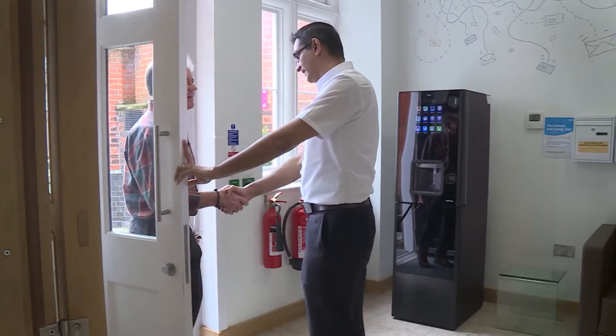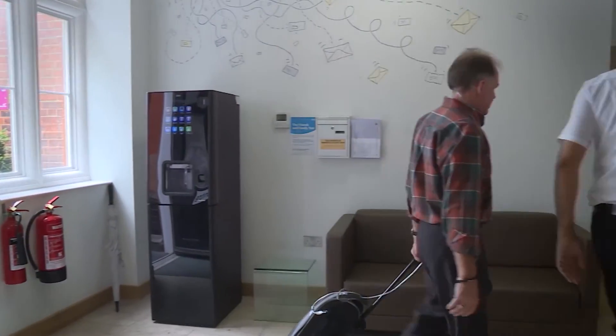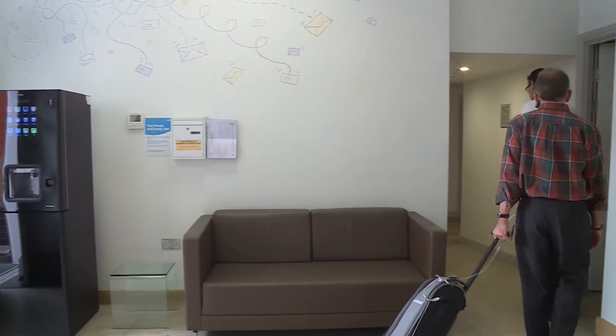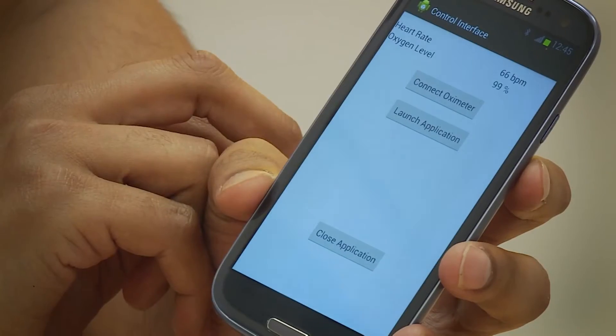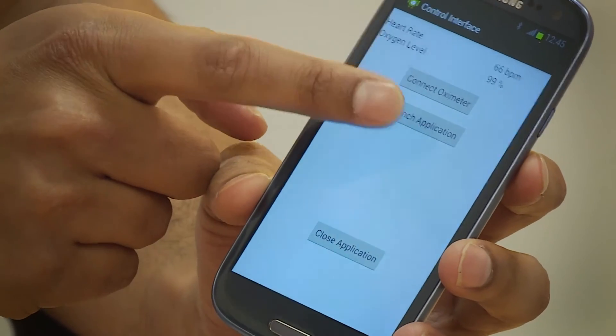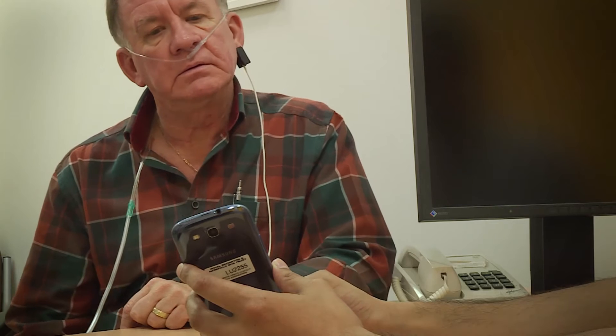So what we've devised together with our colleagues in biomedical engineering at Imperial College is a device that delivers variable flow, and that flow matches the patient's needs. They wear an oximeter that allows us to know their oxygen level. That information feeds via a mobile phone which has a computerised algorithm to a flow device which will then vary the flow — a sort of intelligent flow of oxygen to exactly meet the needs of the patient.